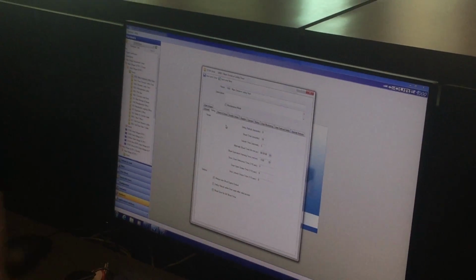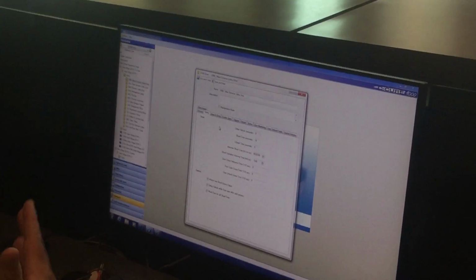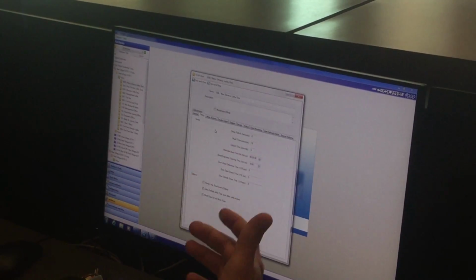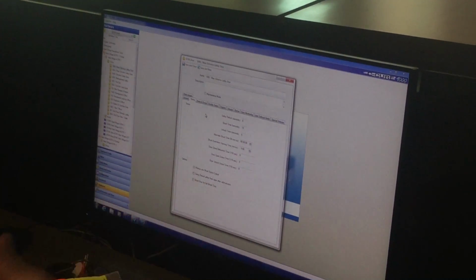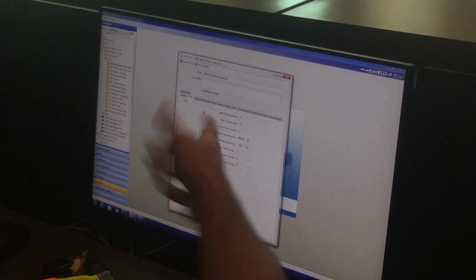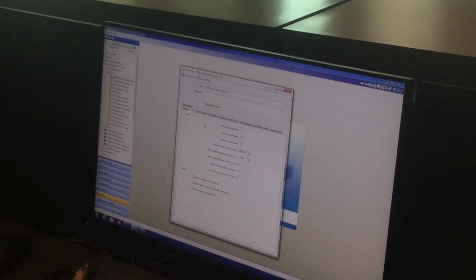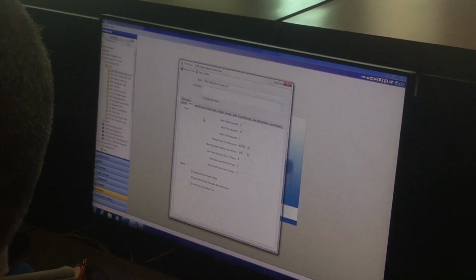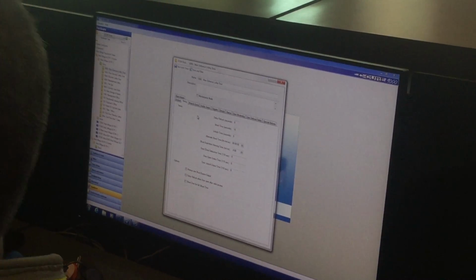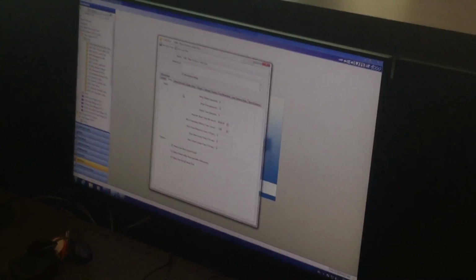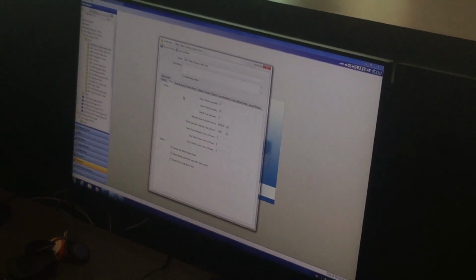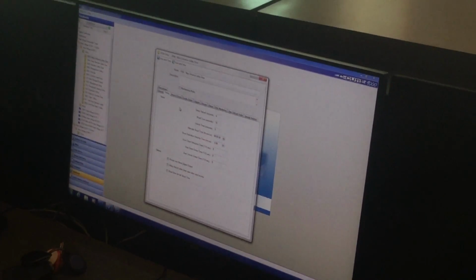Just keep in mind when those doors close, the default programming on the door: you badge the door, you open it, it's going to stay unlocked for 5 seconds. The shunt time on the front lobby here is 10 seconds. So when the door closes, the contact makes back up, then the door is going to automatically relock. You can actually delay the relock to expire when the shunt time expires.